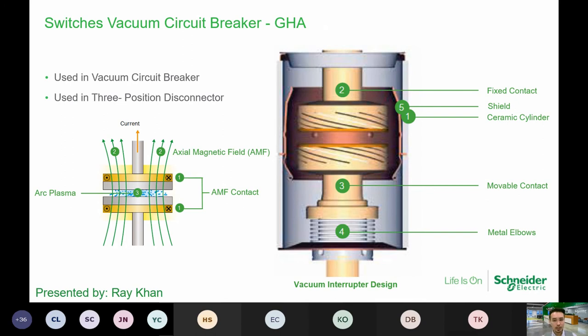The vacuum interrupting chamber is constructed using a material called chromium alloy, and it uses a ceramic cylinder. The purpose of the ceramic cylinder is to prevent condensation from taking place, and also because vapors are easily created during switching. When the vacuum interrupter switches on and off, arc plasma is created as well. That is why we have this technology called the AMF, the axial magnetic field, which is a Schneider technology. It is designed in a way to equalize and diffuse the arc. So this is a simple overview of the vacuum circuit breaker.